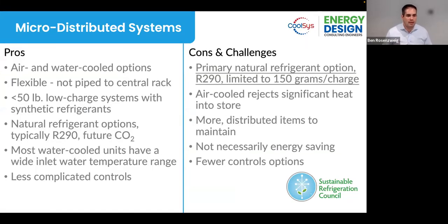So some of the pros and cons about micro distributed systems are different than those of traditional distributed systems. While many of the pros are similar, but played even further upon, there are air and water cooled options, and you can use both in the same store for flexibility. These cases and coils are not piped to central racks, so you have physical flexibility in relocating and adding new cases to your store. All system charges in micro distributed systems are lower than 50 pounds. There are many natural refrigerant options. Typically now, R290 or propane is one of the most popular. However, I will talk at the end here about a CO2 application with a micro distributed system, which is really, really interesting and may be widely popular in the future.